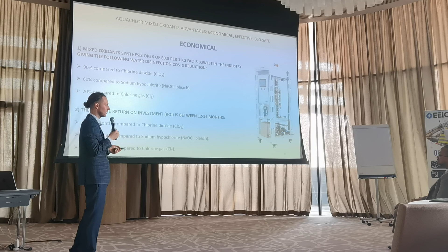The OPEX consists of softened water - 8 liters per 1 kg of active chlorine. We consume 1.8 kg of salt, which is a very efficient number, and around 4 kilowatts of power per kg. So this is basically your main OPEX.